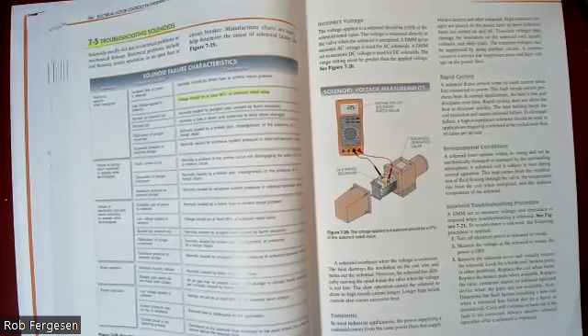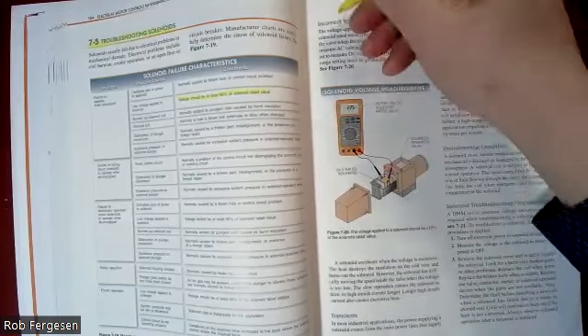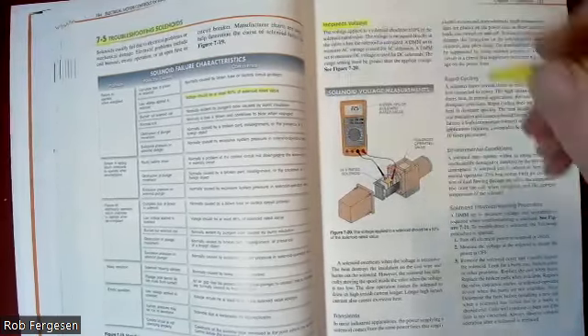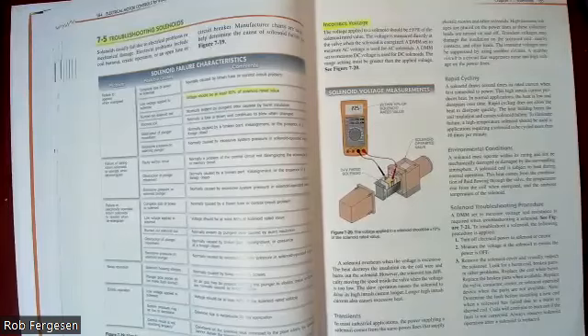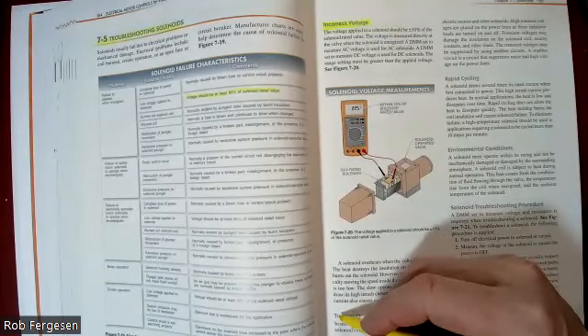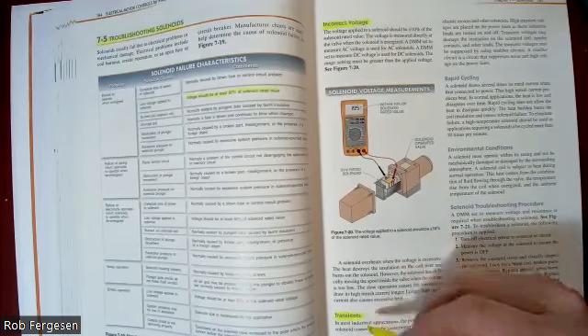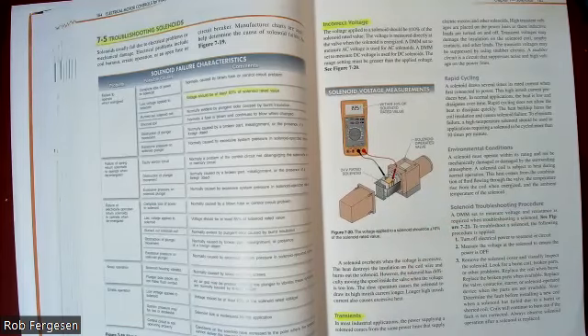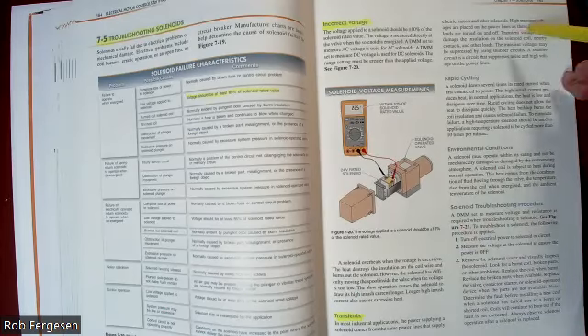It also mentions, I forgot to highlight this, incorrect voltages, which is your classic reason for failure in solenoid valves or relays. But transients means a high voltage or a low voltage that's very brief. A short-term higher or lower voltage, it's transient. And the high voltage is really the killer for these relays and solenoid valves. And so that's the important thing they mentioned here.